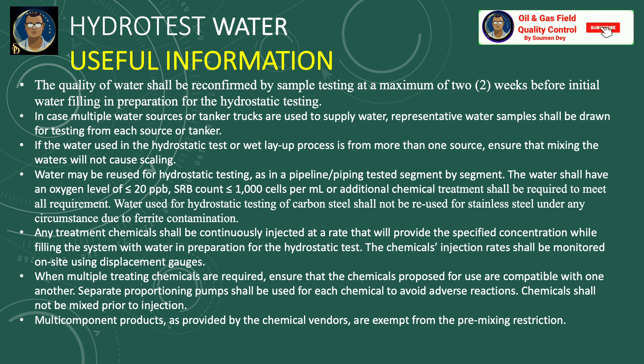If the water used in the hydrostatic test or wet layup process is from more than one source, ensure that mixing of water will not cause scaling. Water may be reused for hydrostatic testing — as in a pipeline or piping test segment by segment — but the water shall have an oxygen level of less than 20 ppb and an SRB (sulfate reducing bacteria) count less than or equal to 1000 cells per milliliter, or additional chemical treatment shall be required. Water used for hydrostatic testing of carbon steel shall not be reused for stainless steel under any circumstance due to ferrite contamination.